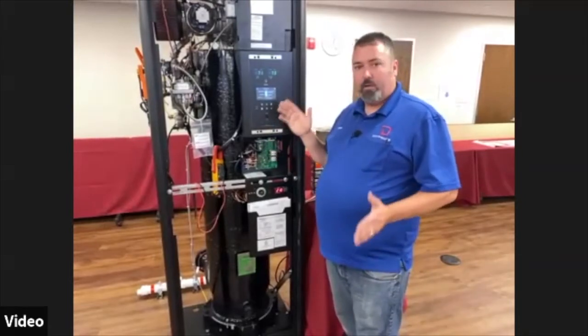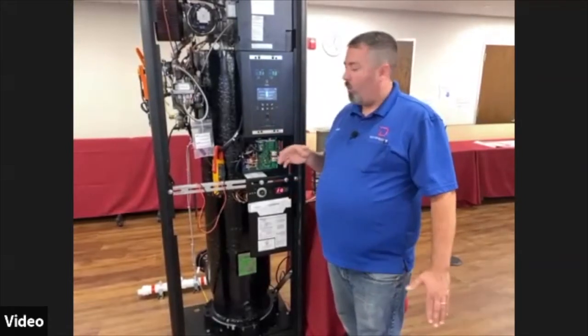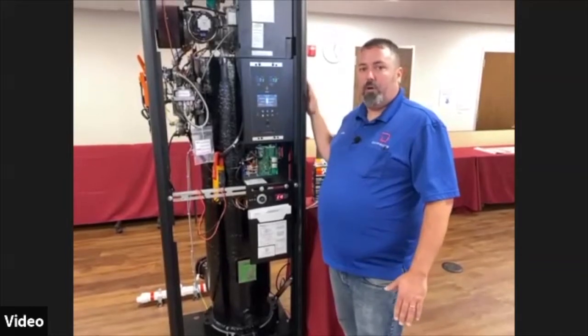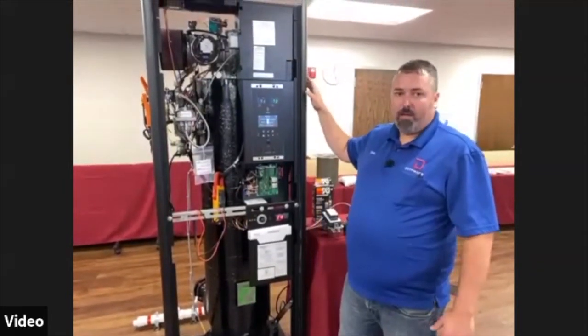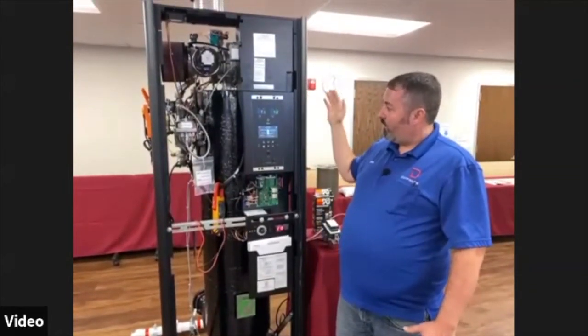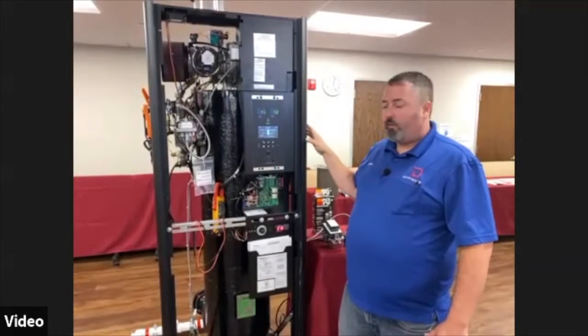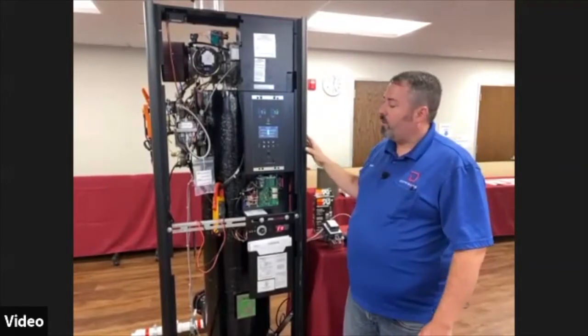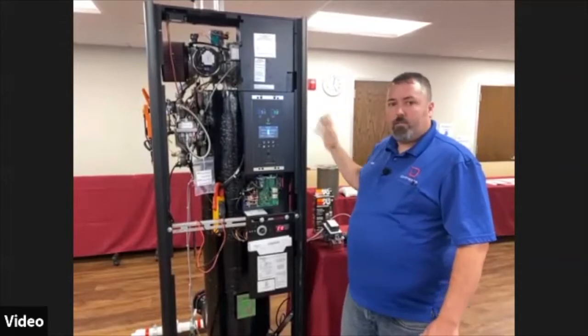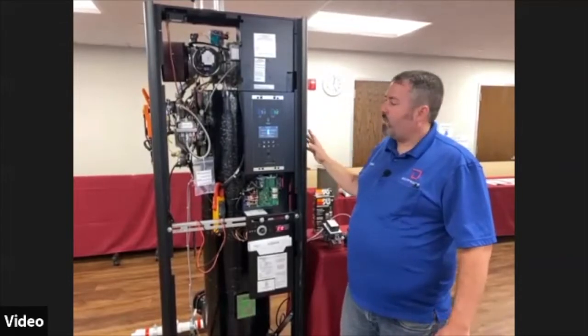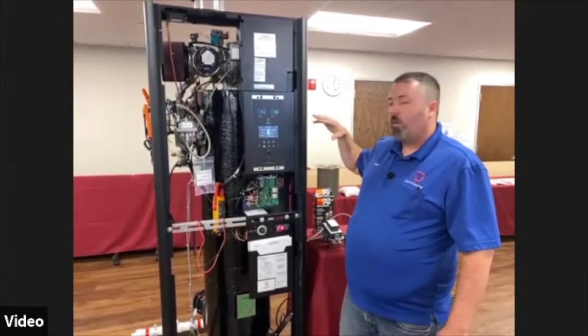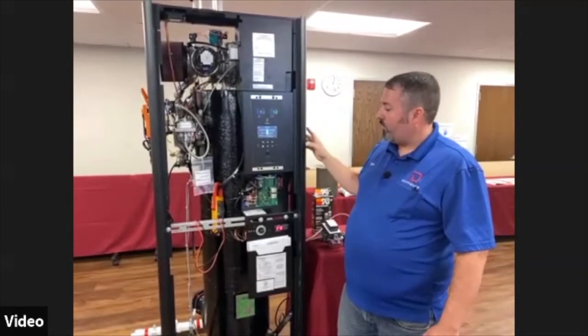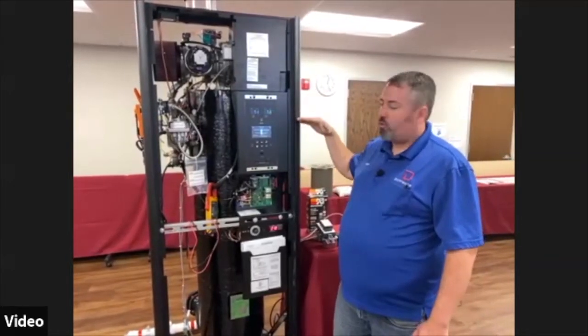After the 2-minute timer and the valve is in the proper position and open, we will go into our purge counter. The blower will come on full speed, and the air valve will open, and we'll push air for 30 seconds through the heat exchanger. That's used to purge out any possible gases from the last firing sequence. Once the purge counter is done and we've purged for 30 seconds, we'll go into our ignition trial.